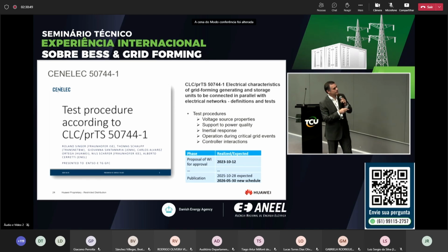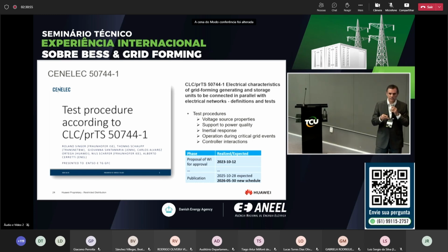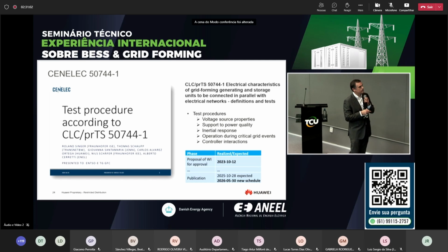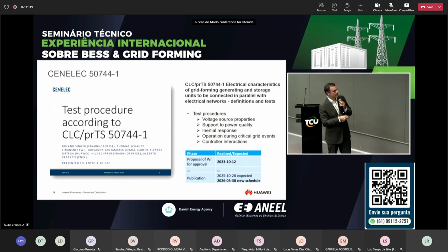We have been talking about the requirements like inertia, short circuit contribution, power oscillation damping, but how to measure this is not so well defined yet. So that's the main point of this standard, at European level. Just to remember, if the standard starts with 6, it's IEC, international level. If it starts with 5, it's European level.